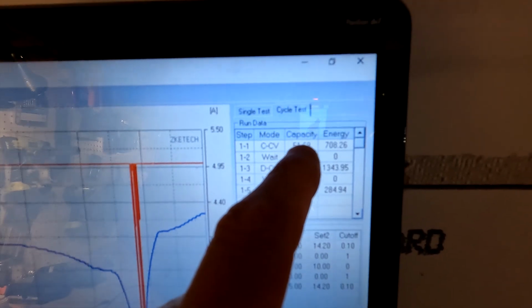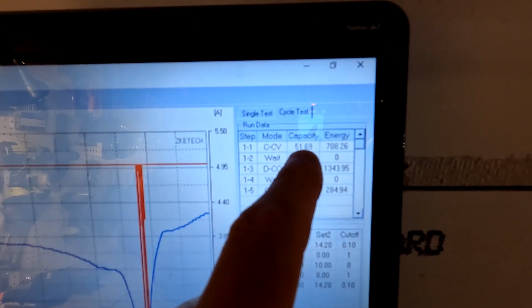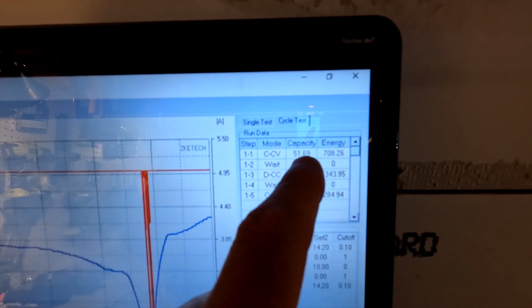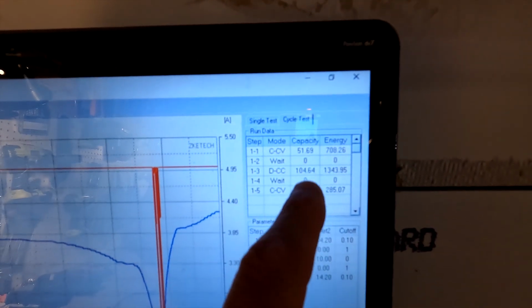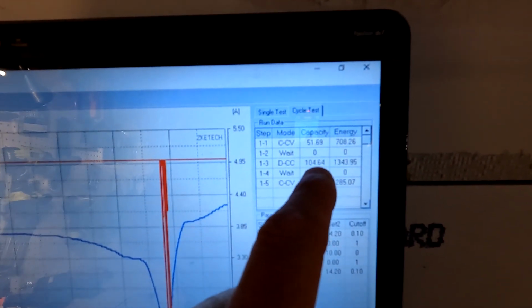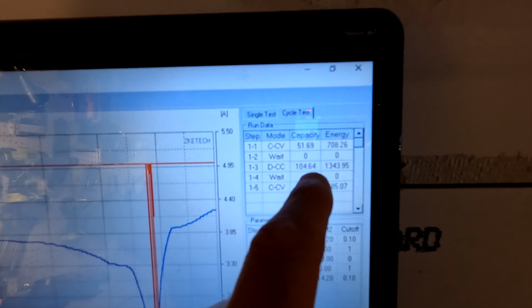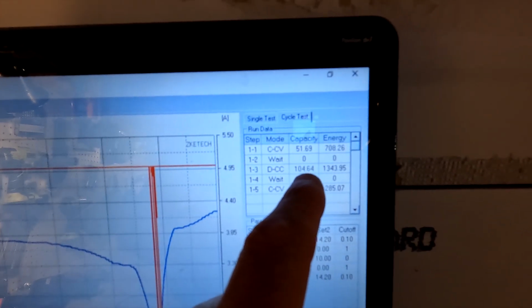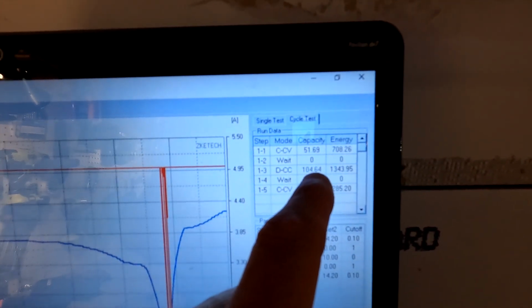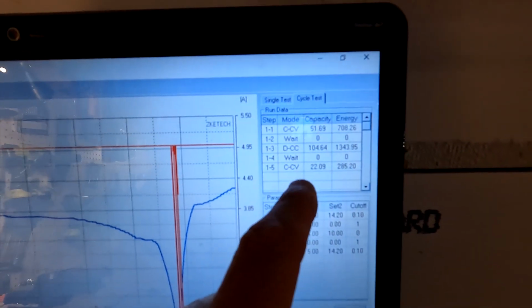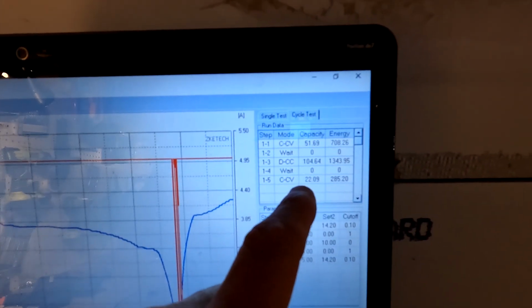You can see right here in this line, first it charged, it put 51 amp hours into the battery, so the battery was right at 50% when I received it. And then it discharged 104.64 amp hours. So out of a 100 amp hour battery, that is perfect. That's exactly what you want to see. And currently it is charging it back up.